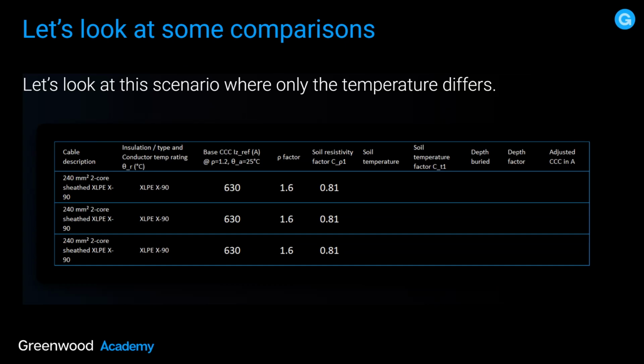So let's look at this scenario where only the temperature differs. We're looking at the first column, cable description. I've got three options. Well, actually, they're all the same. It's 240 mil cable, 2-core, right? The same insulation type and conductor temperature rating. You've got your base current carrying capacity of 630 amp. You've got your P factor at 1.6 with the resulting soil resistivity factor of 0.81. Soil temperature of 15 degrees. Soil temperature factor of 1.06. It's actually gone up, right? Depth of bury 0.8. Depth factor 0.96. You've got an adjusted current carrying capacity of 519 amps.